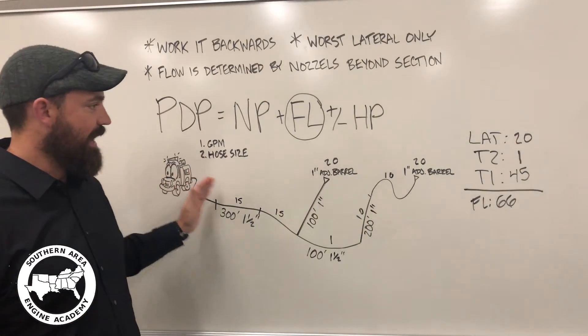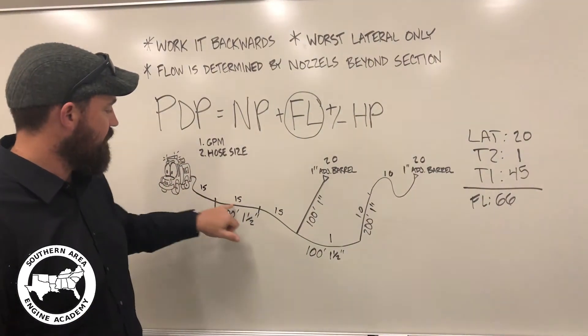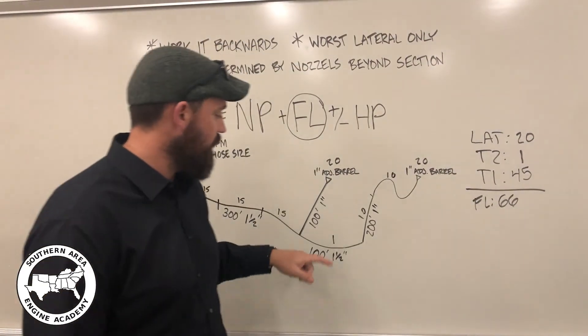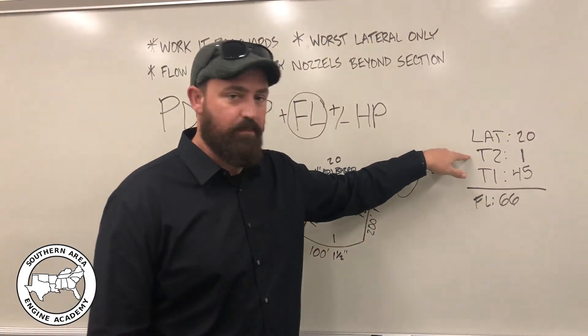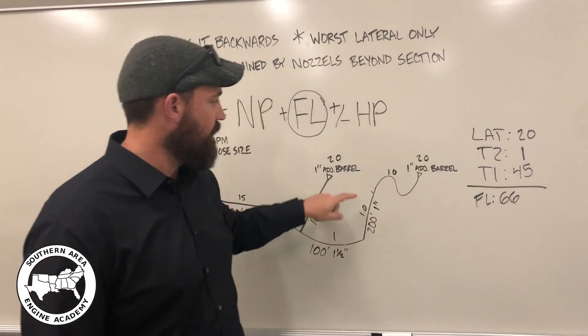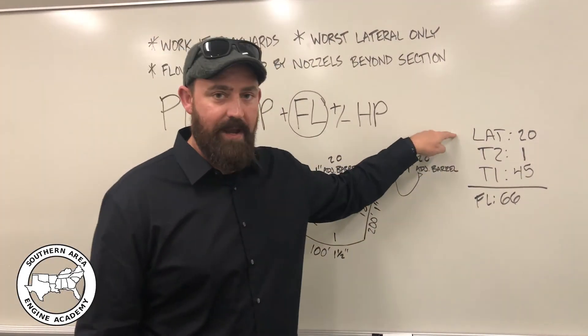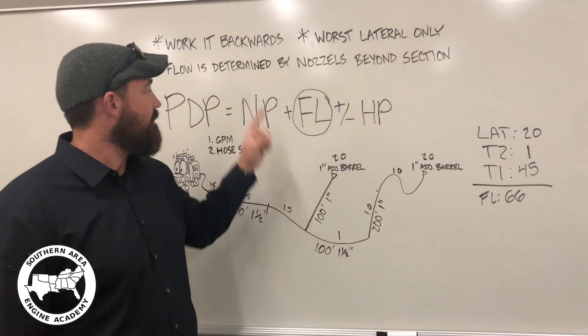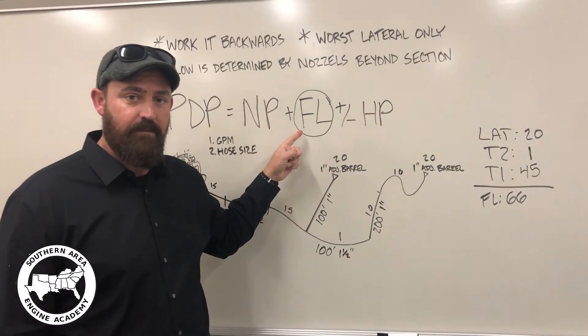So, as we added it up, we see three sections of 15 pounds, that's how we got our 45 pounds of loss for trunk one. Trunk two was one pound of friction loss, and the lateral was losing 20 pounds for a total friction loss of 66 PSI. And that is the FL component of the equation.